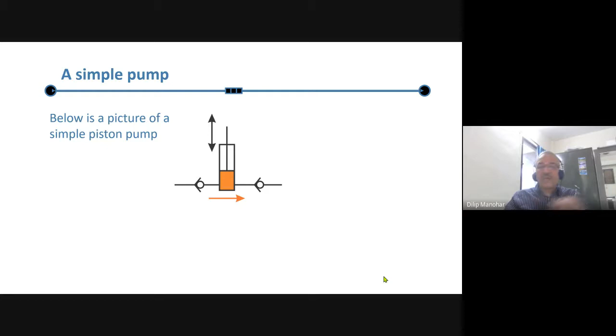Here there's an analog design. A simple pump shown is a piston pump with two check valves, inlet as well as outlet. On the inlet stroke, that means when the handle is actuated, the piston rises. That means we are sucking the liquid inside. It creates a vacuum here. This side is a suction line.